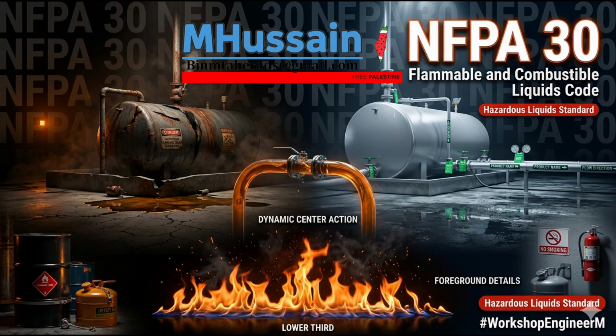Why 30 gallons, though? What's the math behind that specific number? It's all about potential energy yield. If 30 gallons of a Class IA liquid were to spill and completely vaporize, which it wants to do at room temp, that resulting vapor-air explosion has enough force to literally blow out the structural walls of a standard-sized commercial room. Oh, wow. Yeah. 30 gallons is the calculated threshold where the energy release surpasses standard structural resistance. Now, for Class IB and IC, because their boiling and flash points are slightly higher, that unsprinklered limit bumps up to 120 gallons. But 120 gallons is still just about 2 drums.